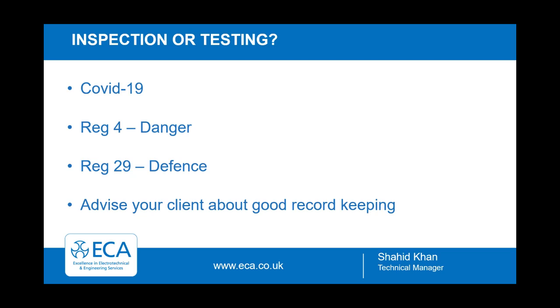So, if the HSE was to investigate an installation following a serious incident, the burden of proof would be on the installation owner to prove that they took all reasonable steps and exercised all due diligence in maintaining their electrical systems to prevent the rise of danger. Hence, record keeping of regular periodic inspections is crucial in providing that defence.